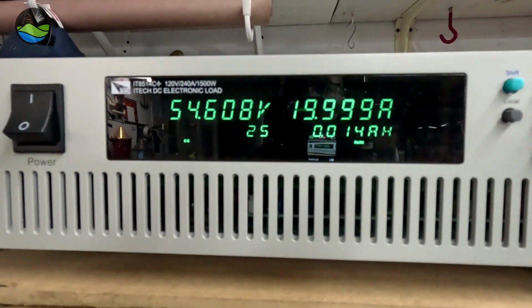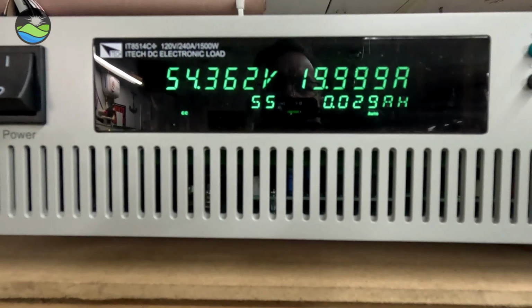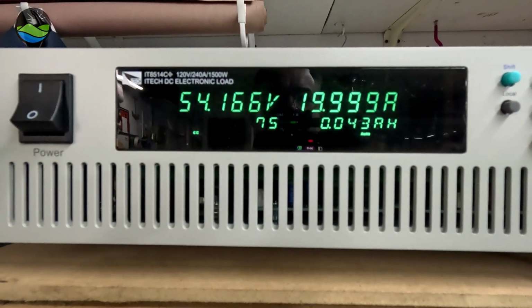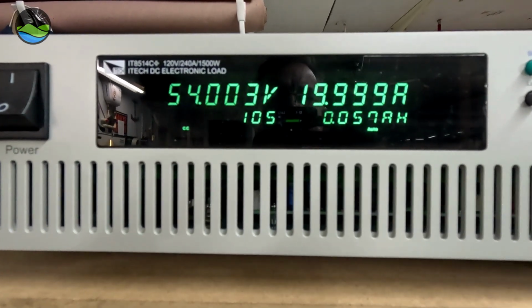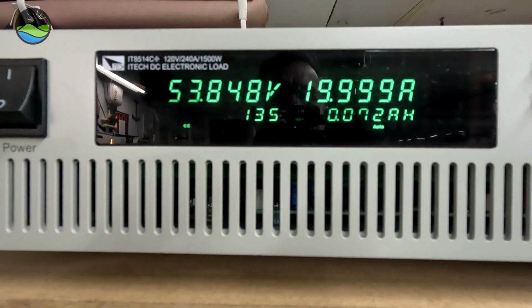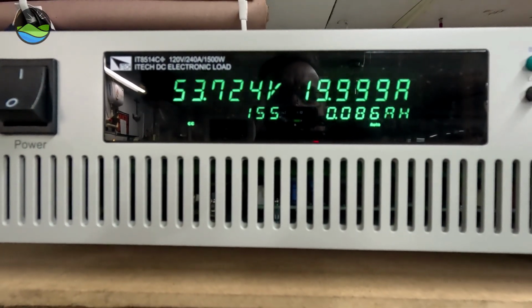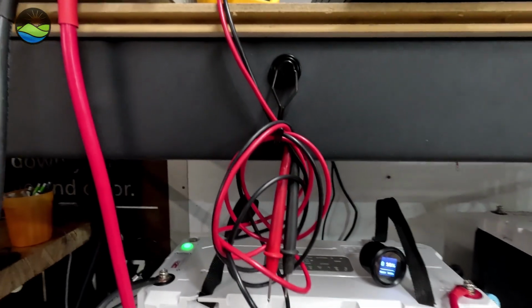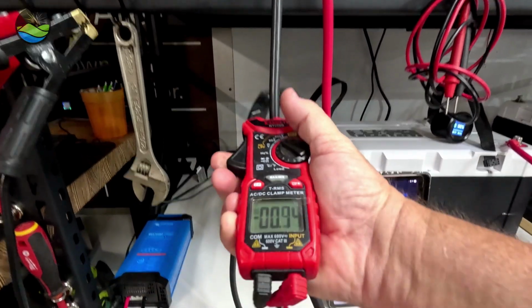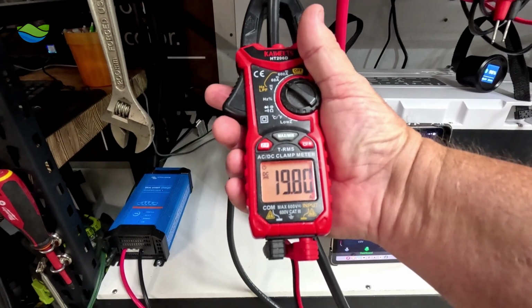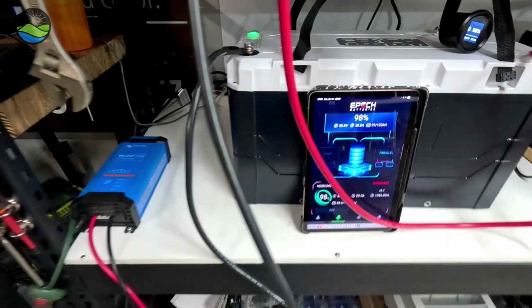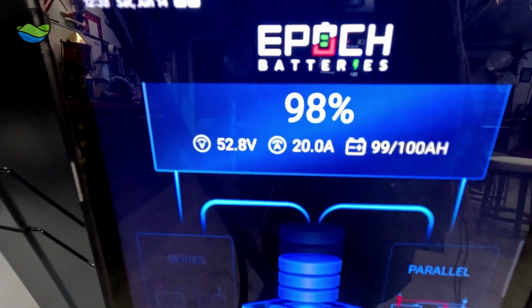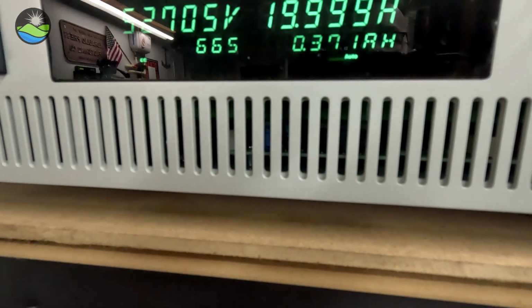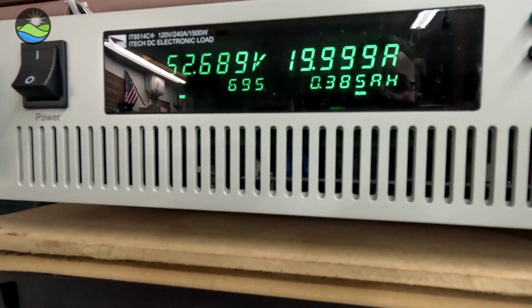And so we are pulling 19.999 amps, counting the amp hours to 3 digits. Let's check it with the clamp meter here. That machine up there is way more accurate than this clamp meter. So we're showing 20 amps here and 19.999 there. So that's good enough.